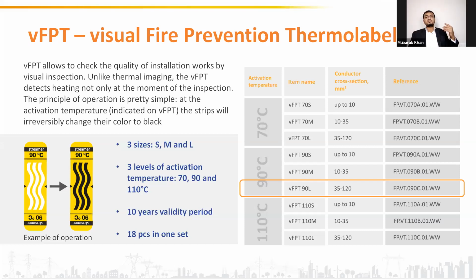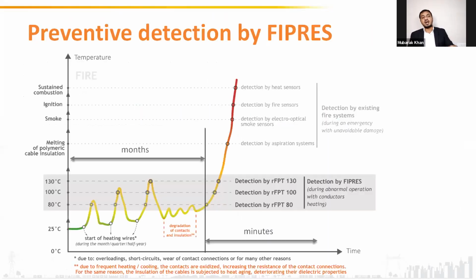Okay. This gives you 24/7 monitoring, but you will only get the alert when you go and inspect it physically. The stickers are available in 70 degrees Celsius, 90 degrees Celsius, and 110 degrees Celsius, in various sizes: small, medium, and large. Okay. Now preventive detection, let us see whether our motive is achieved or not. By using a remote fire prevention system or visual fire prevention system, we are able to detect the abnormality in the range of 80 to 130 degrees Celsius. And that is why we are able to eliminate any fire scenario which may occur in future, right? So the purpose of using this kind of system is achieved by using this fire prevention system.